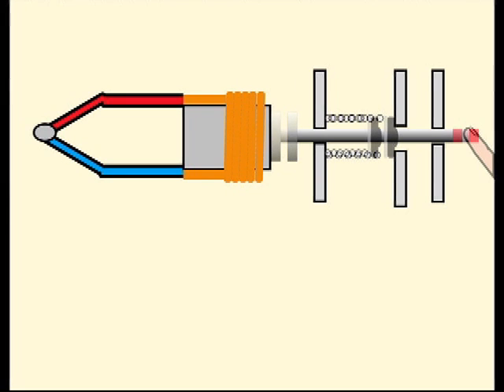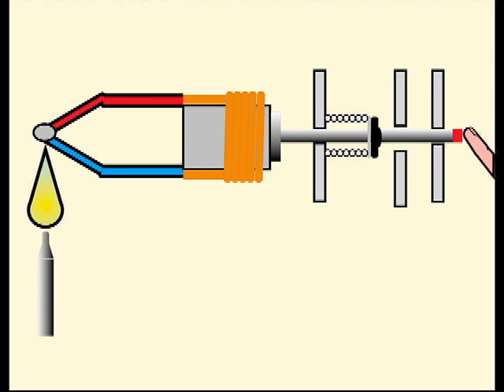When we wish to turn on the heater, we have to press first the start button. This will push the iron plate until it touches the ferromagnetic core. We turn on the pilot flame and wait about 30 seconds until the thermocouple delivers about ten thousandths of a volt and the core is magnetized enough as not to let go the iron plate.